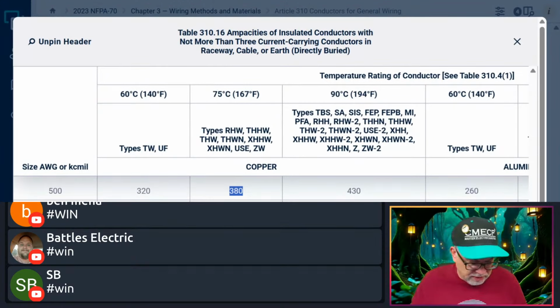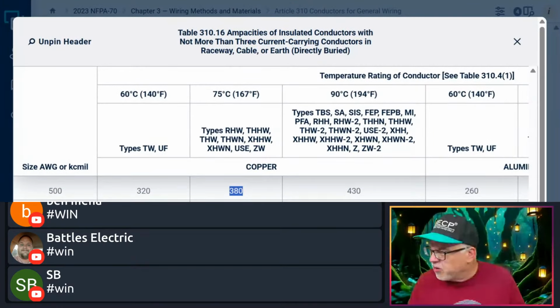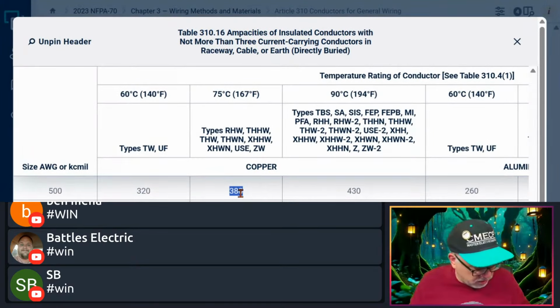So we're just kind of looking at what we're doing. We weren't given any ambient temperature, and we can get to the number of current-carrying conductors, and we can look at that as well. But let's kind of work this entire thing out. All right, so first, 380 under the 75. So what's 380 times 3? Because it was 3 sets of 500. Well, that's 1140. 1140 is not 1200. Okay, so we looked at that.